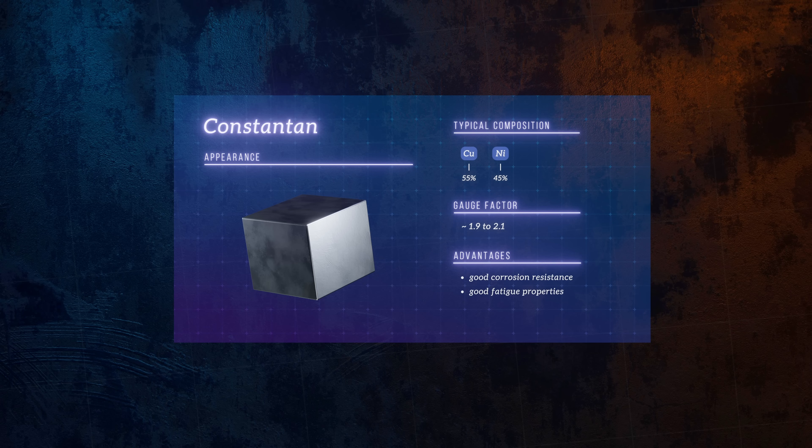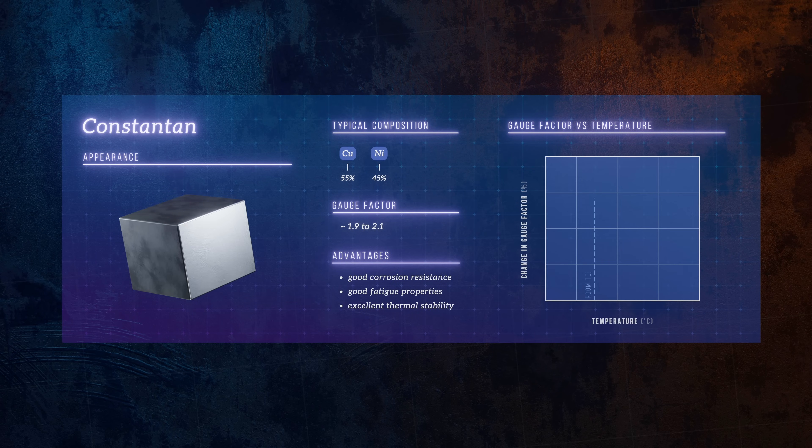But the main reason it's such a good choice is its performance over temperature. Most materials have a gauge factor that varies significantly with temperature, which makes it difficult to get accurate measurements when working with large temperature ranges. But Constantan is very stable. Its gauge factor varies very little from minus 50 to 150 degrees Celsius and beyond. In fact, that's where the material gets its name. And that's the main reason it's the most popular material for use in strain gauges.